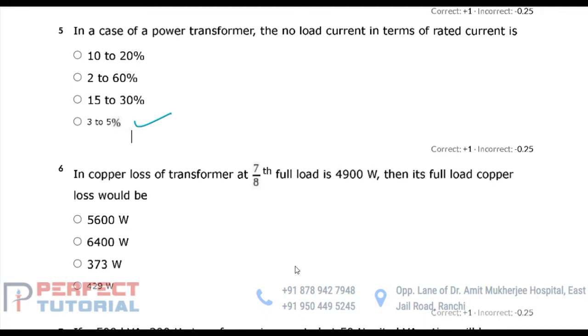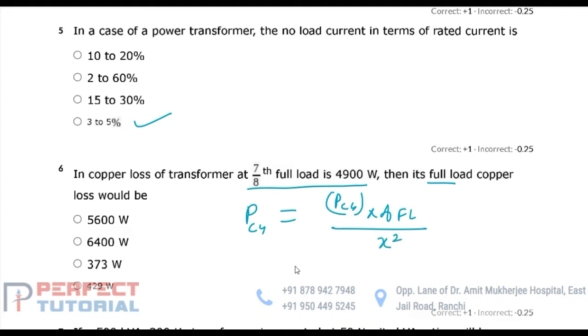Next problem you see, in copper loss of transformer at 7 by 8 of full load is 4900 watt, then its full load copper loss would be. देखिए दिया हुआ है 7 by 8 ऑफ फुल लोड पर कॉपर लॉस 4900 वाट है। देन इस ट्रांसफार्मर में होने वाला कॉपर लॉस क्या होगा फुल लोड पर। अब कॉपर लॉस at x of full load मालूम है, देन फुल लोड पर मालूम करना है। आप जानते हैं कॉपर लॉस at full load is equal to copper loss at x of full load divided by x square. यहाँ पर x का वैल्यू 7 by 8 है. So just to put the values, it will be equal to 4900 divided by 7 by 8 whole square. It will give you answer as 6400 watt.